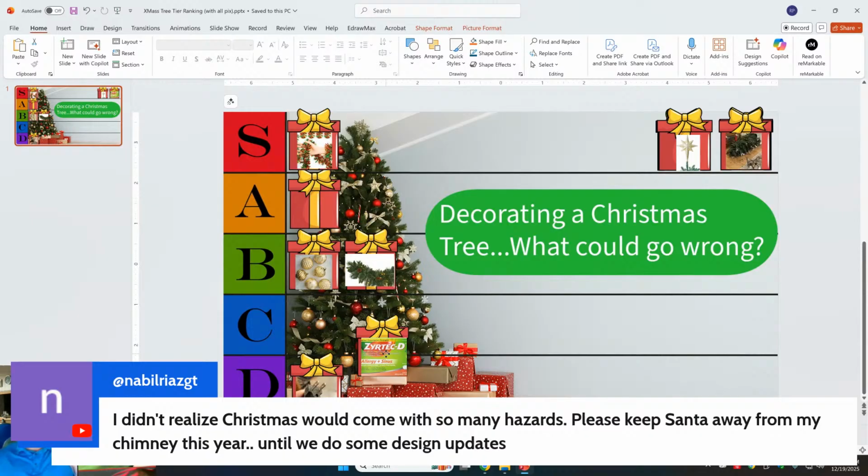So when we do biocompatibility testing, we have different types of exposure. You have implantation, we have external communication, we have surface contact. This is going to be more like the surface contact because the person has nose hairs that are supposed to filter out things. They're not supposed to be eating the Christmas tree. That would be an extreme case of abnormal use.